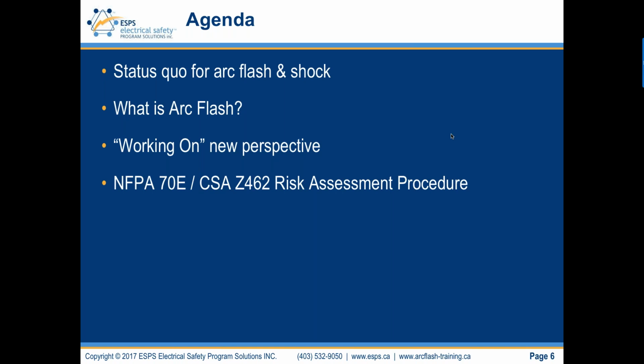Working on the definition in 70E and Z462, a bit of a new perspective. So I'll just highlight my current thinking on that topic, and this will help us hopefully move to clarifying arcing fault probability and arc flash, and when the worker is really exposed versus not exposed and there's no need for arc flash shock PPE. So again, we'll broach that topic.